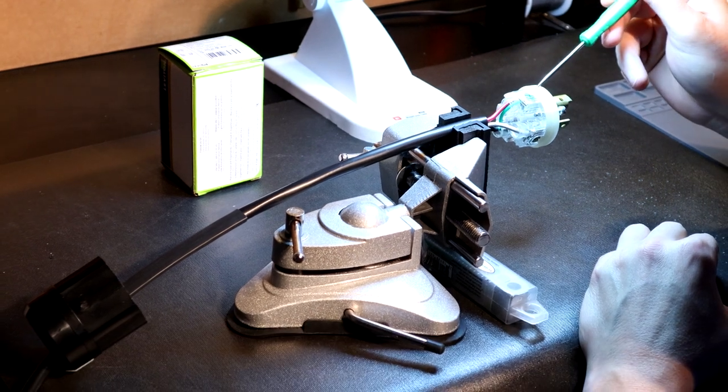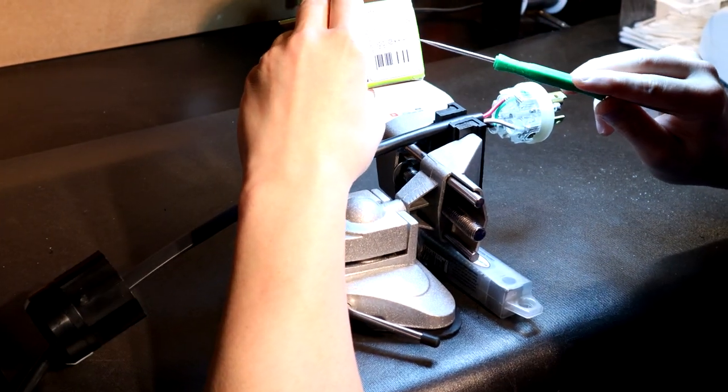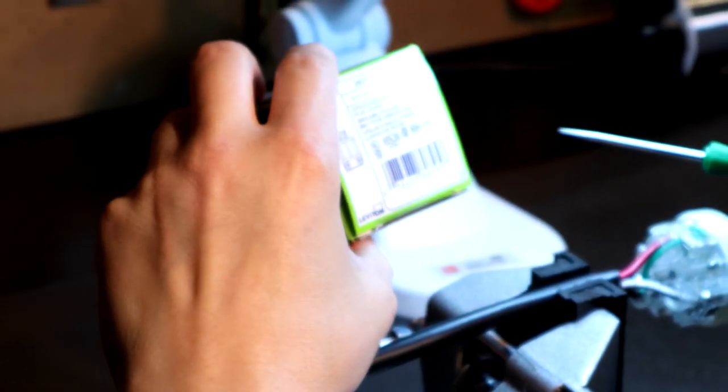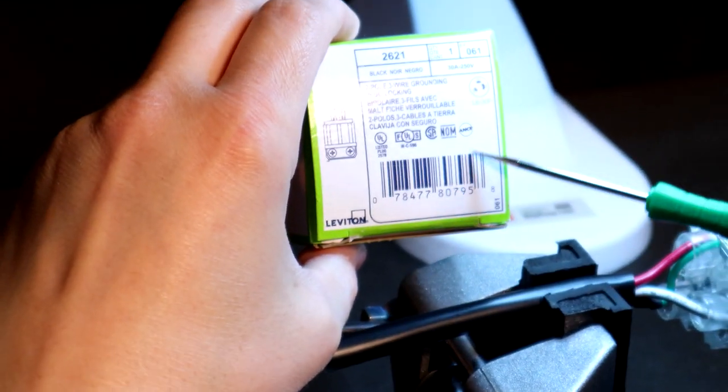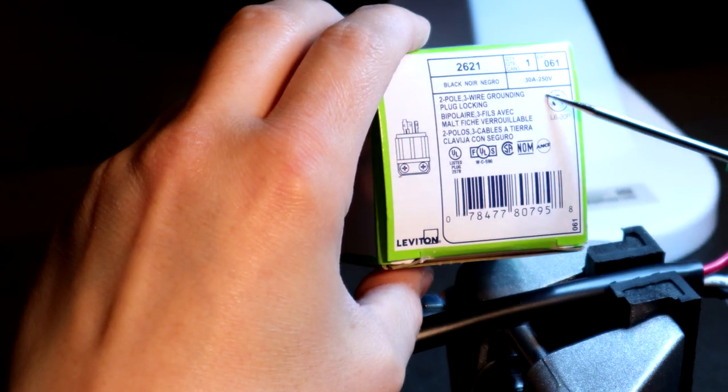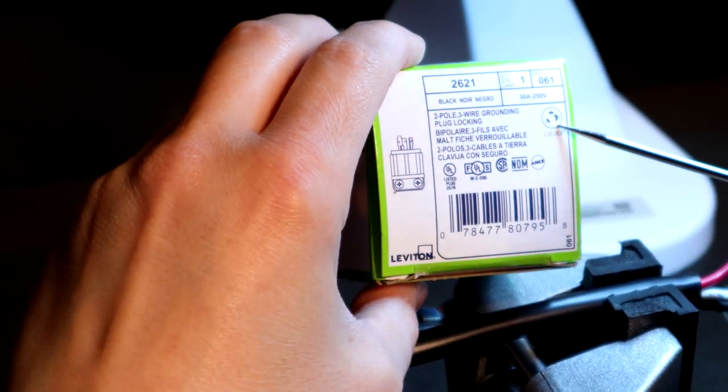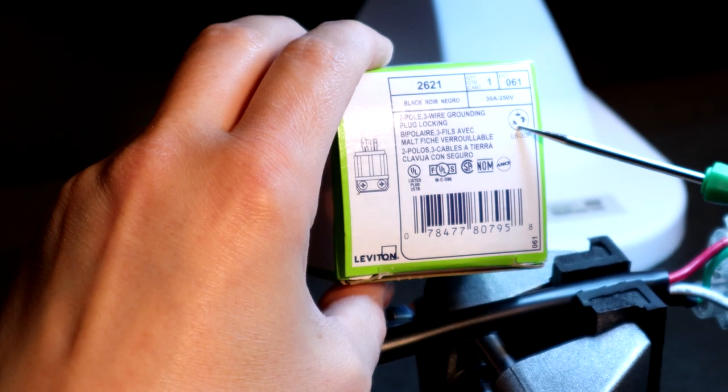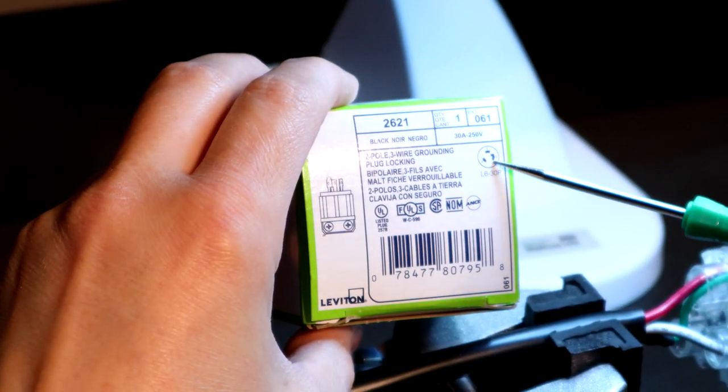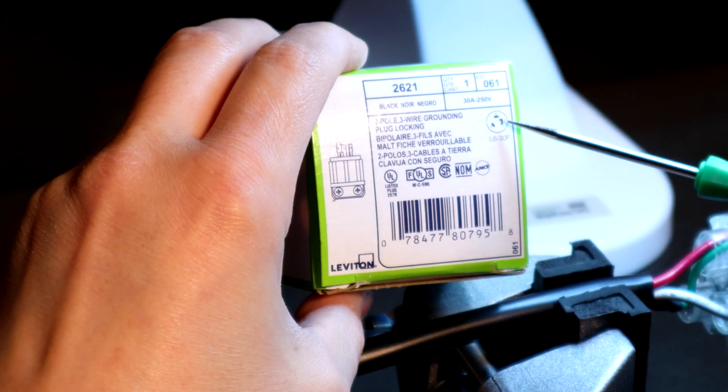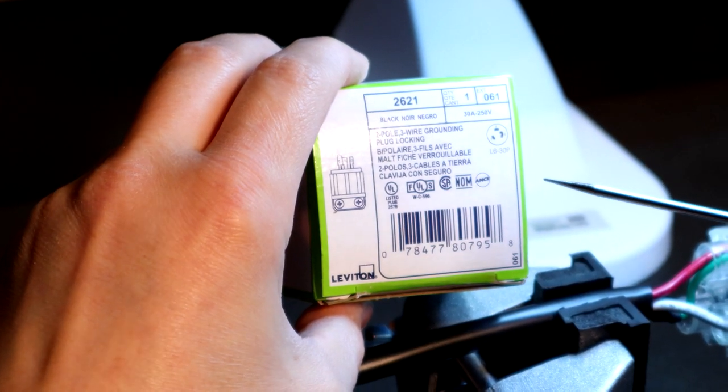This cable is unique because we're using a NEMA plug, an L630P from Leviton. Very nice connector. I get a lot of questions on these plugs and I want you guys to pay close attention. Right here is the box for the plug. One of the biggest questions I always get asked is there a wiring diagram for the plug. If you look closely on this box right here as I'm pointing, there's a Y, an X, and a G. The G symbolizes ground. The Y and X are for power.